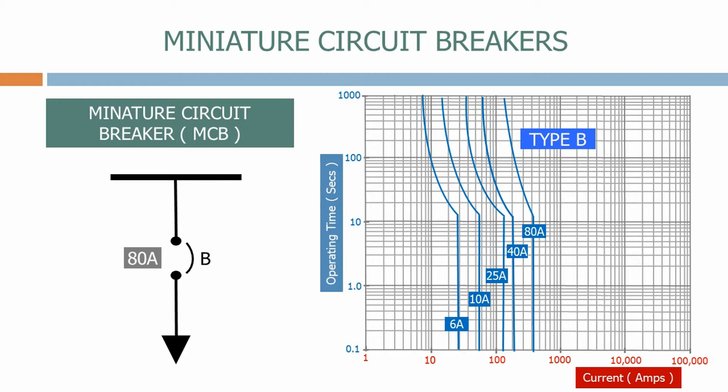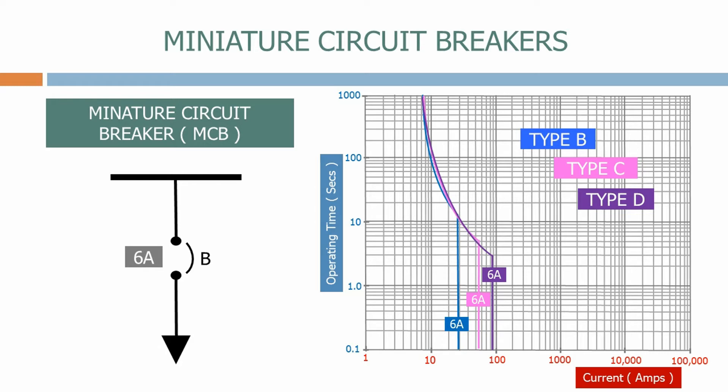Let's now look at a 6 amp rated type B MCB. If we compare it to a 6 amp rated MCB from the type C and type D family you can see the difference between the characteristics. As we can see the slope of the curve is similar to all three families but the type D MCB will trip instantaneously at a higher current level.